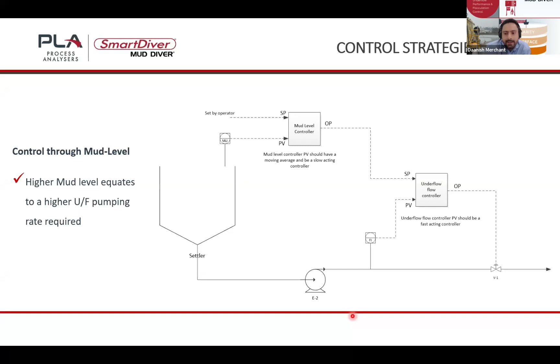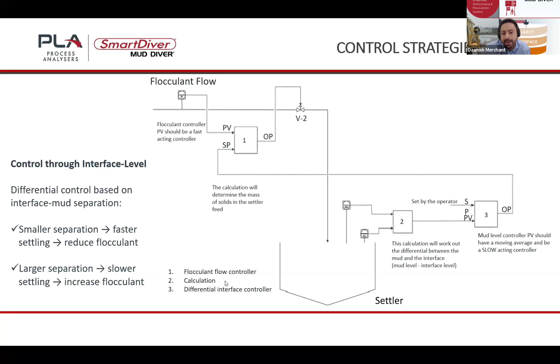Similarly, flock dosage can be adjusted based on bed levels, and a differential control strategy can be implemented depending on the separation between the mud and interface layer. Smaller separation indicates faster settling, suggesting a reduction in flocculant, while larger separation indicates slower settling, where adding more flocculant can bridge that gap. This is an oversimplified version of how these levels are optimized, and if the gap narrows too much or widens a lot, it can be corrected using bed level measurements.